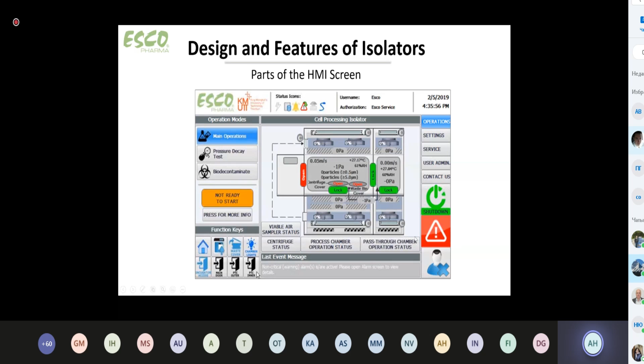So the operation will be the main one, the pressure testing, the biodecon. You can have a very graphical representation of the isolator, and you can change to check the status of the individual equipment. Example, viable air sampler, centrifuge, process chamber, pass-through chamber, microscope, whatever, okay? This menu can go on and on. Okay, that's the HMI.